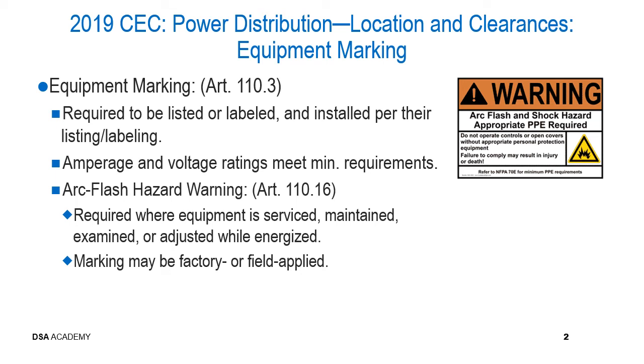labeling. Project inspectors need to be sure to review and verify that the amperage and voltage ratings meet the minimum requirements for the project and also match the submittal information that was provided by the design team / contractors. Additionally, where equipment may be serviced, maintained, examined, or adjusted while it is energized, arc flash warnings are required to be applied to the equipment. The details for these arc flash warning markings are included in Article 110.16, and these markings may be factory or field applied.